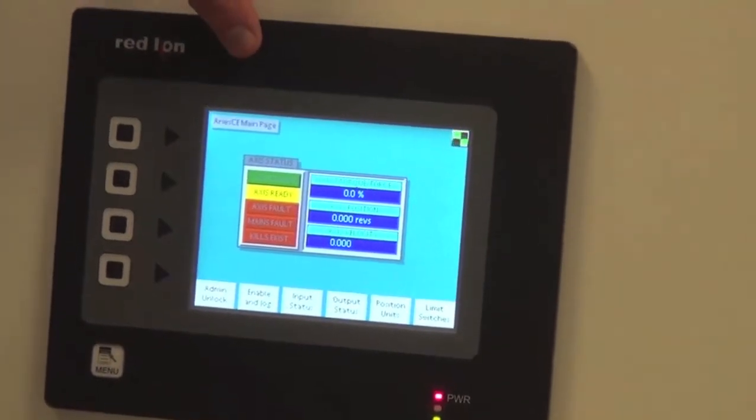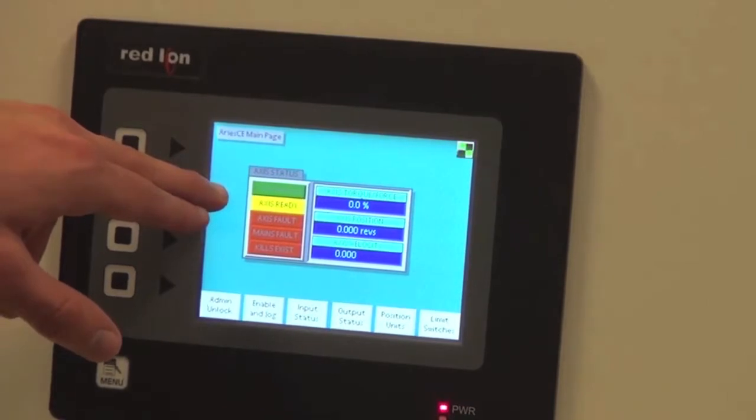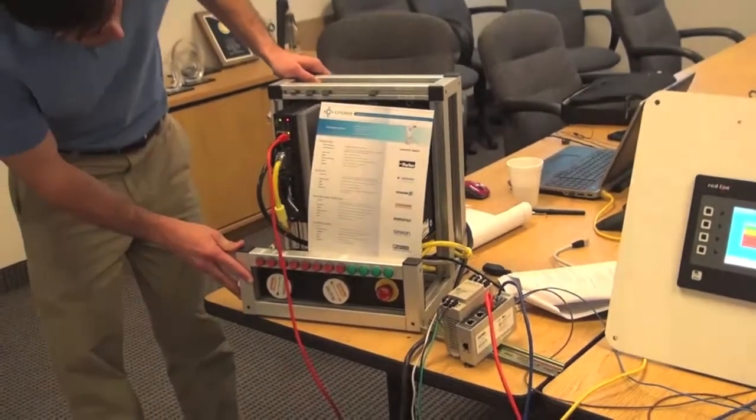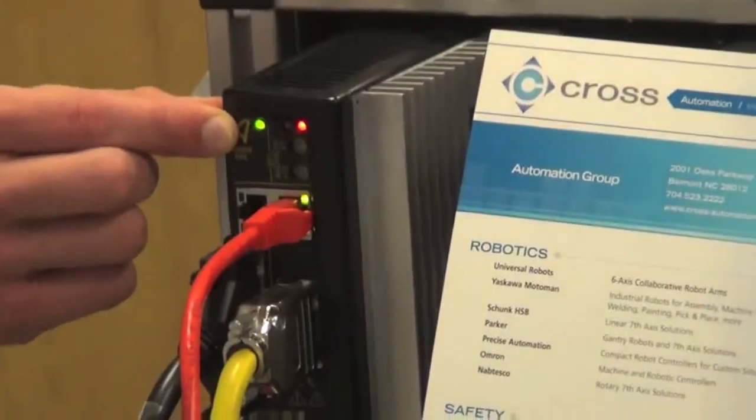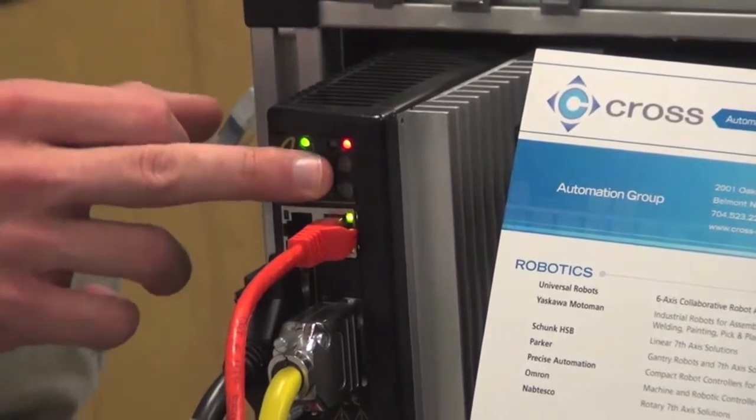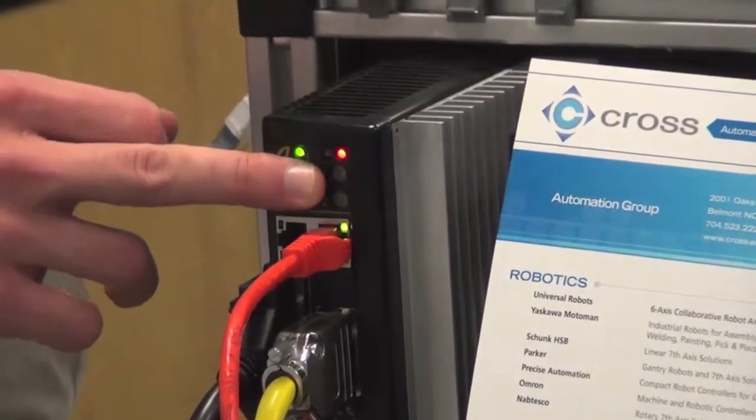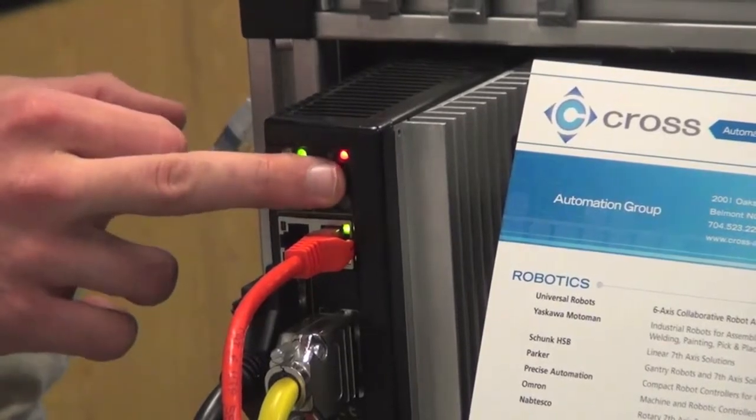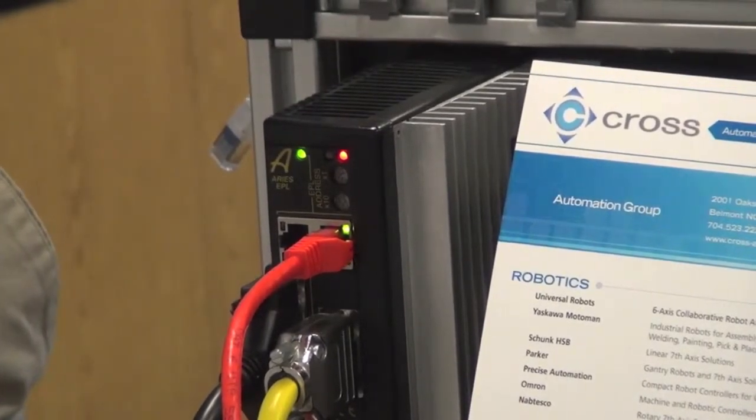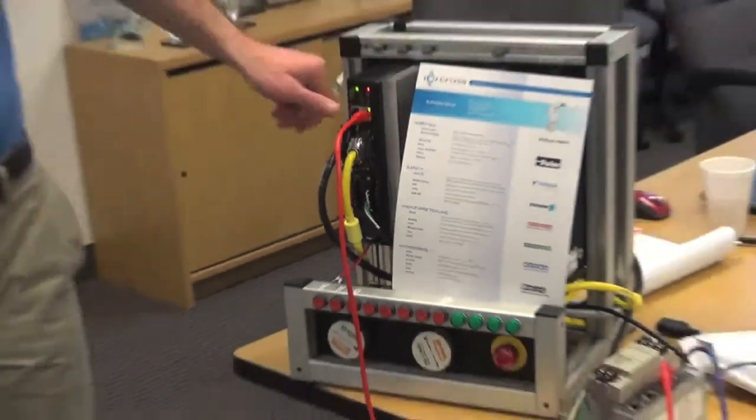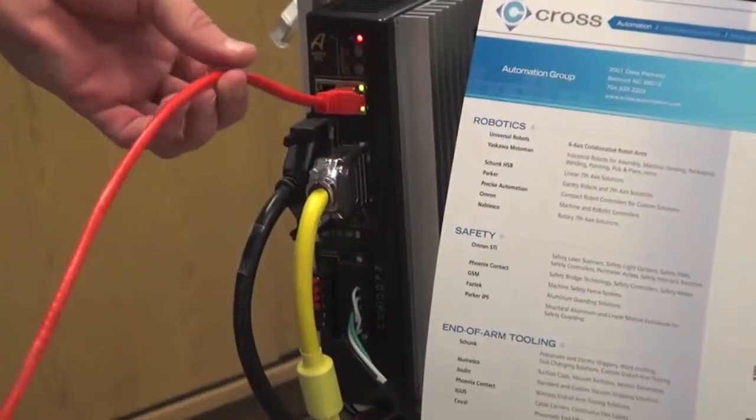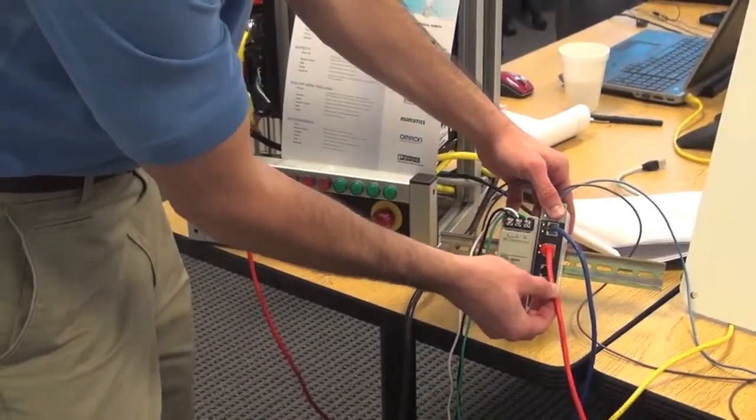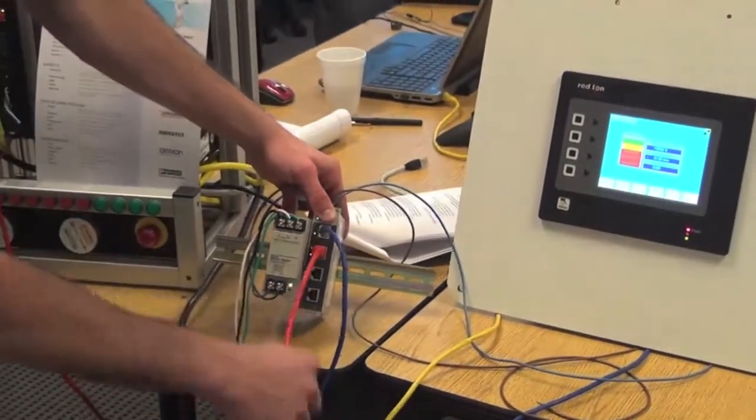Now the main page is up and shows that the axis is ready. If you pan over to the drive we can look at a few lights that are important to note. This light shows that it's getting communications. The middle light shows various faults and problems the drive may encounter - it is off right now. This light shows that the drive is disabled. When enabled it will have power to the servo motor and torque enabled. You can see lights flashing on the ethernet cable and port showing they are indeed communicating and talking back and forth between the Red Lion and the drive.